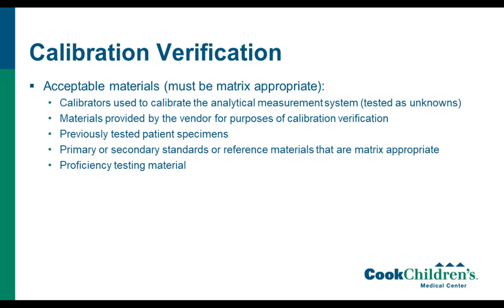For calibration verification, acceptable materials must be matrix appropriate and include, you can actually use the calibrators that you use to make your initial standard curve by running them as unknowns. You can use preferably a different lot number, but that doesn't always necessarily have to be the case.